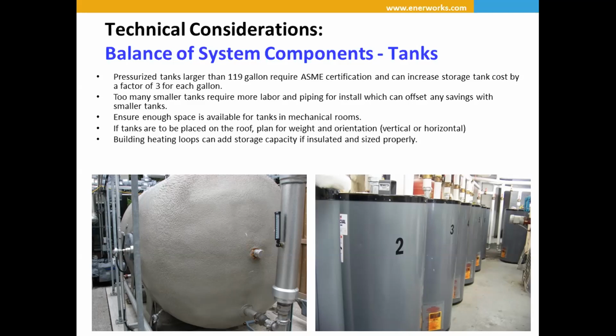And so at a certain point, it makes more sense to go with the larger tanks. Some companies will opt for the smaller tank. The system on the right, you can see they had to use 16 tanks because it was a basement of an apartment where the tank was going. So they didn't have an option to use a larger tank there. The one on the left is actually an outdoor application with a horizontal tank. So it's just something to consider. I know in California, the seismic requirements are often such that you have to have a horizontal tank. So it's important to identify that early on. And the weight of the tank can also be a problem on the roof. So it's something to make sure to bring up.